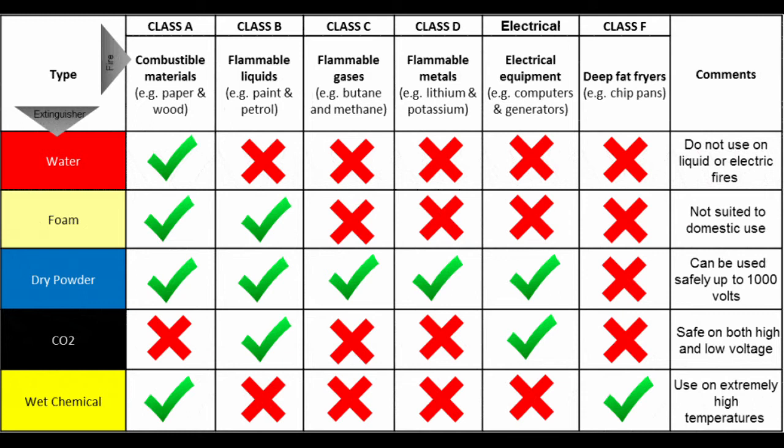They should be placed on a dedicated stand or hung on a wall at a convenient height so that people can easily lift them off, at about 1 metre for larger extinguishers, 1.5 metres for smaller ones, to the level of the handle. Ideally, no one should have to travel more than 30 metres to reach a fire extinguisher. If there is a risk of malicious use, you may need to use alternative and more secure locations. Where there are self-contained small premises, multi-purpose extinguishers which can cover a range of risks may be appropriate.